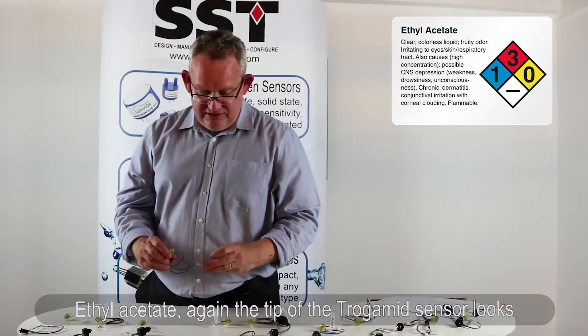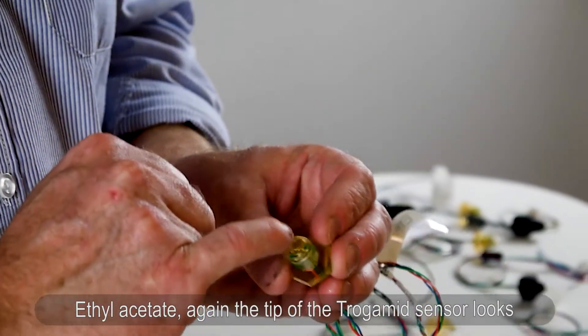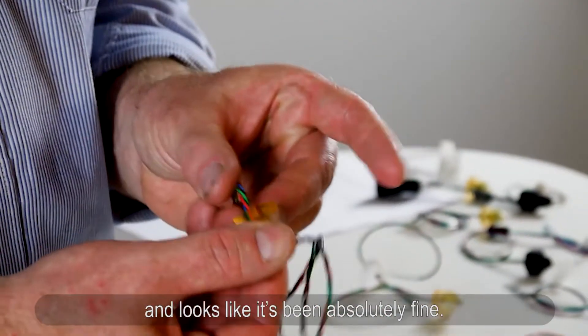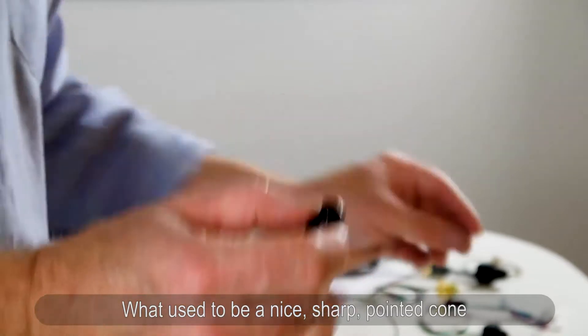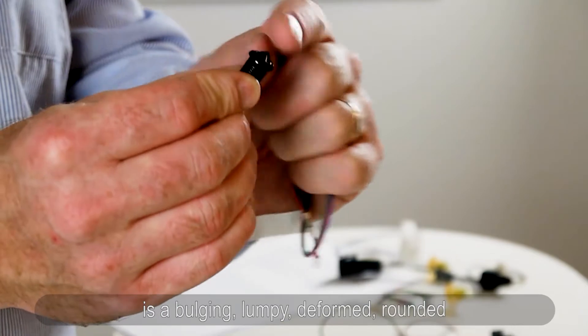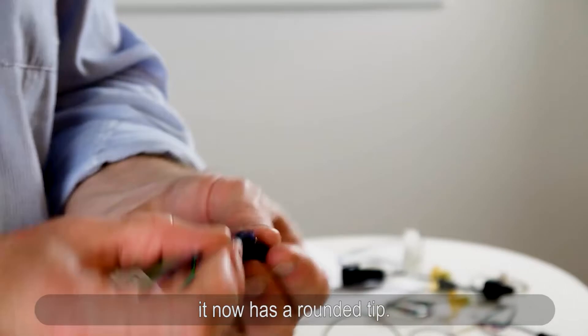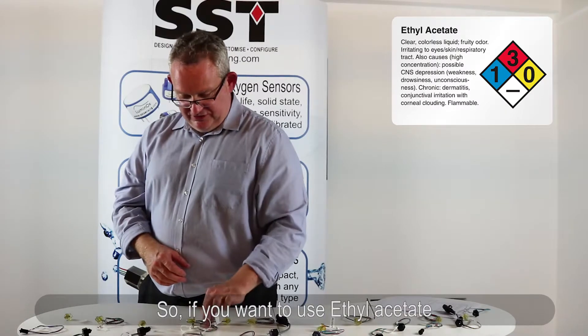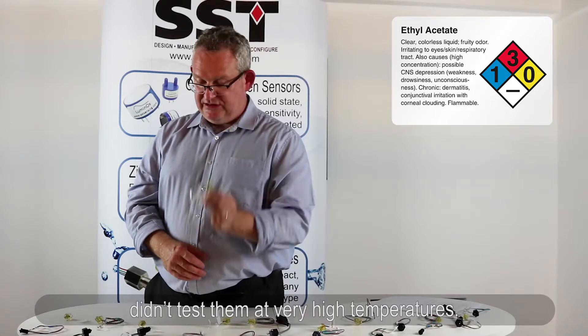Ethyl acetate — the tip of the Trogamid sensor looks nice and shiny, perfectly untouched, threads look okay, it's been absolutely fine. But the polysulfone has really started to melt. What used to be a nice sharp pointed cone is now a bulging, lumpy, deformed, rounded tip — the whole thing is just not in very good shape. So if you want to use ethyl acetate, Trogamid looks like your option, although we only tested for a few days and not at very high temperature, so you'd still need to do a complete thermal test.